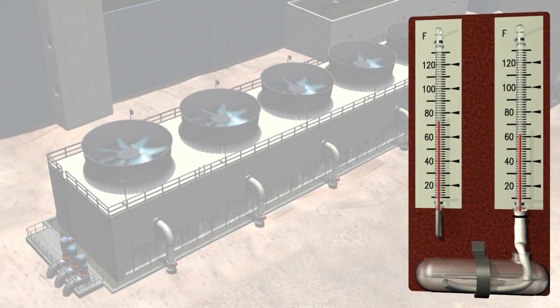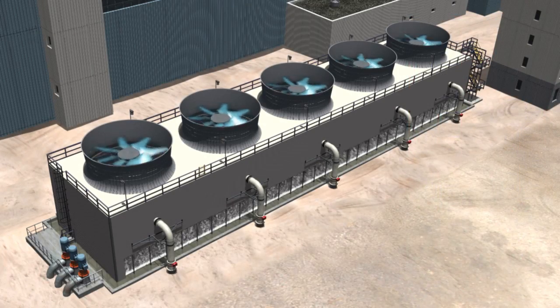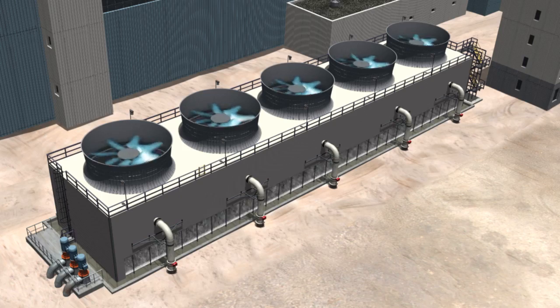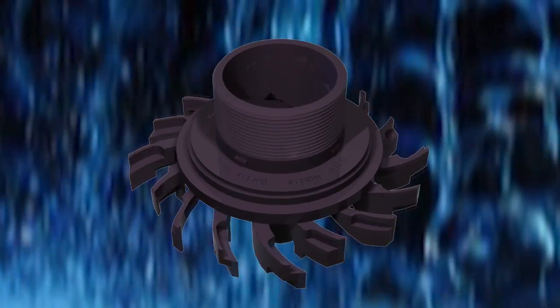As the wet bulb rises, fans and pumps will be cycled back to the on mode. You can now sync the water flow with the fans and track the wet bulb up and down, saving enormous amounts of water and energy by simply installing the Variable Flow Nozzle.